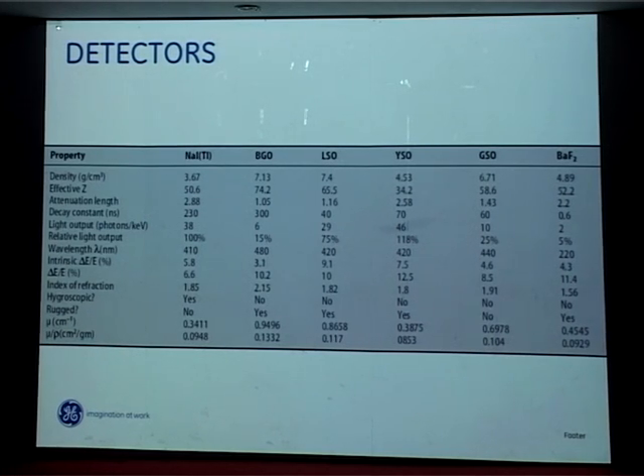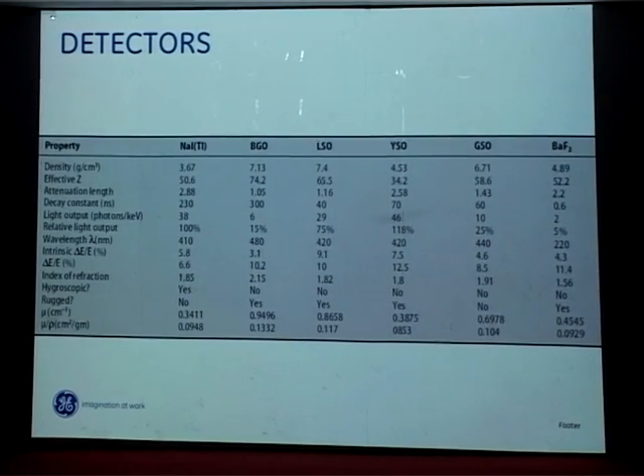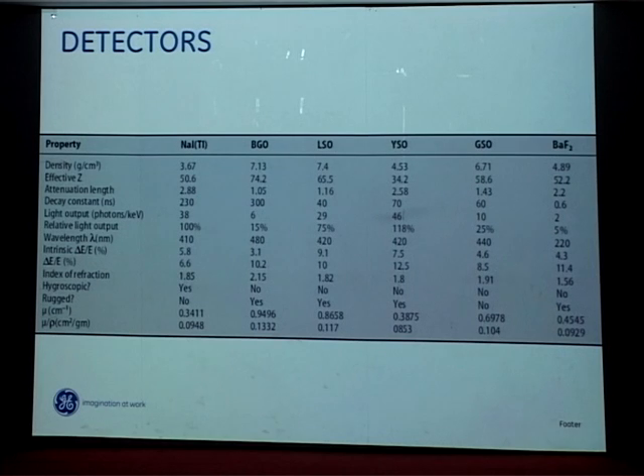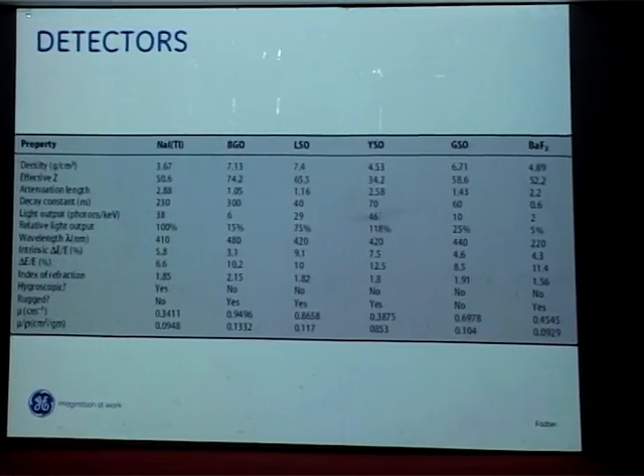Scintillation detectors are used in PET-CT just as in the gamma camera. The most commonly used detectors are BGO and LYSO. For a good detector: high stopping fraction, good light output, and short decay time constant. BGO is mainly used in oncology studies where FDG is the tracer; LYSO is preferred for short-lived isotopes and high count-rate studies where you need to image quickly without losing image quality.